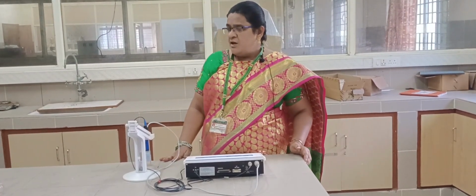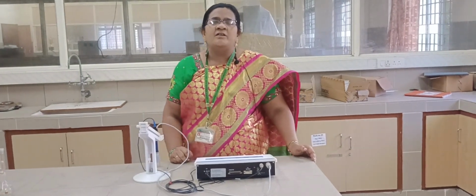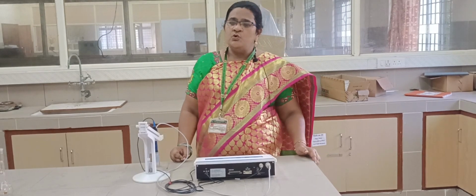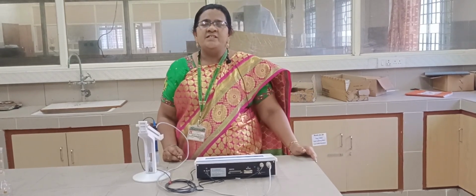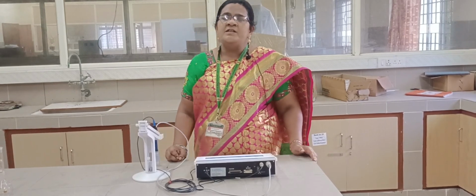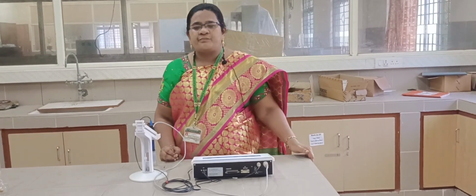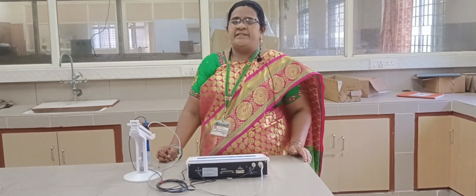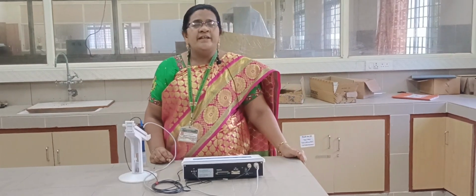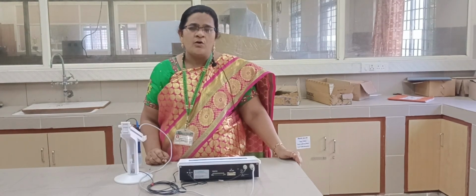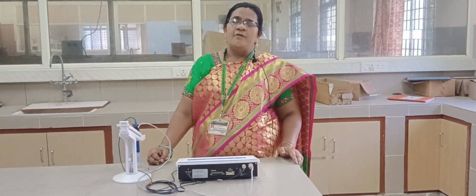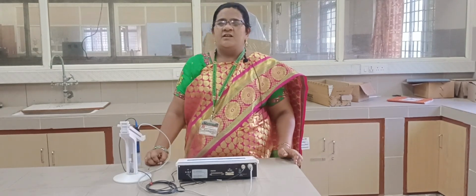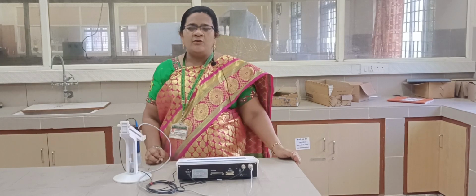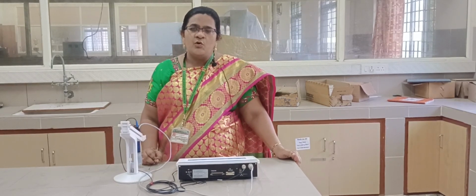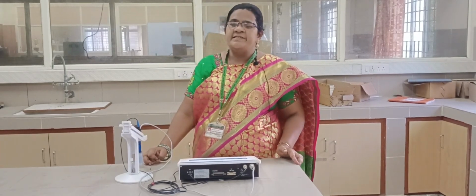Next, maintenance of the electrode is very important. Inside the electrode, saturated KCl solution is present, and the bulb is very sensitive. It's a porous bulb. Always keep the bulb in saturated KCl solution when the instrument is at rest. If we observe any salt formation or oily formation around the bulb, we wash it with 0.1 molar hydrochloric acid for 30 minutes. If there is protein contamination, we wash the bulb with 1% pepsin in 0.1 molar HCl for 15 minutes.